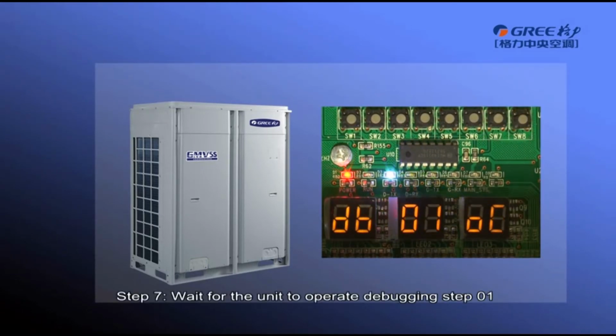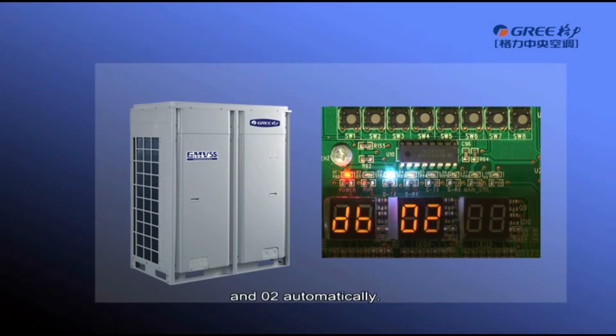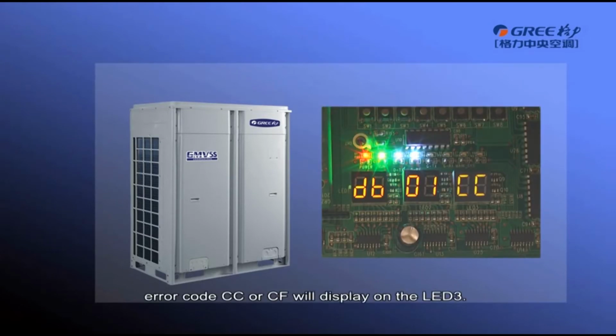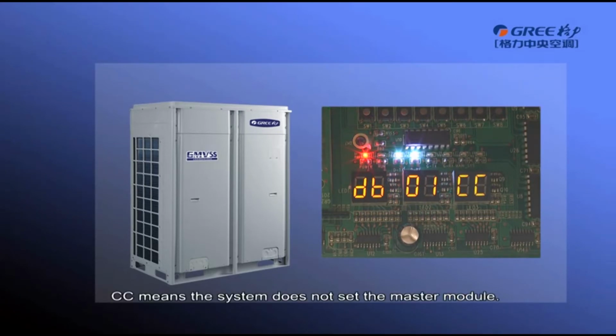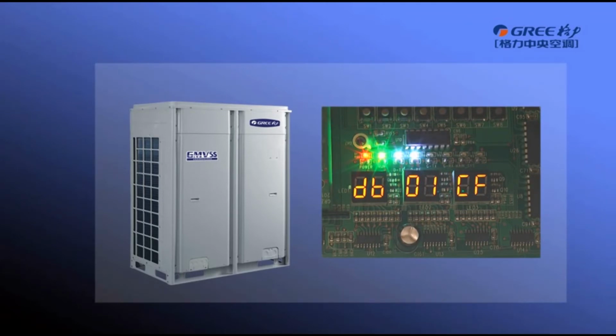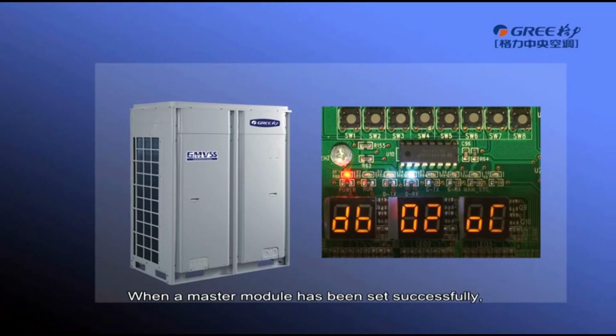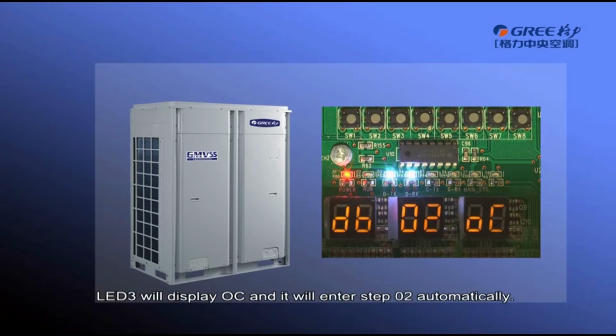Wait for the unit to operate debugging step 1 and 02 automatically. If the master module is incorrect, error code CC or CF will display on LED 3. CC means the system does not set the master module. CF means the system has more than 2 master modules. When a master module has been set successfully, LED 3 will display 0C and it will enter step 02 automatically.